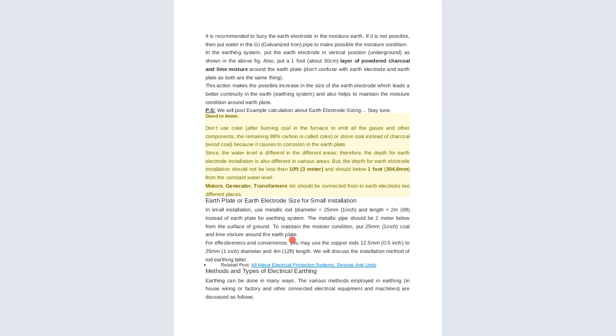So it is recommended to bury the earth electrode in moist earth. If that is not possible, then put water in the GI galvanized iron pipe to make the moisture condition possible. You will realize, if you've ever gone to the field, that people doing installations, the moment they are doing earthing, make sure they align their earth plate, or wherever they bury the earth rod, in line with where the water from the roof normally pours on the ground, so that it can provide the moist condition that is needed for the earthing.